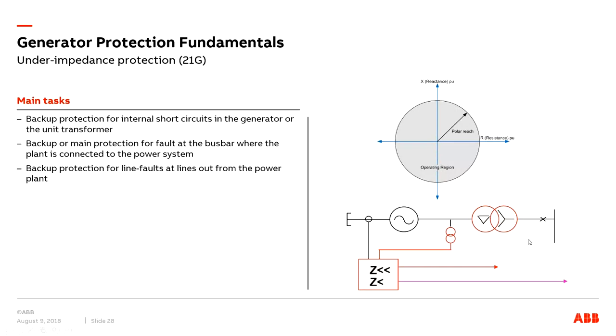Then we have the under impedance protection. The under impedance protection has two different tasks: detection and fault clearance of internal faults in case the main protection, that is the differential protection, fails. And the second task is to detect and clear an external fault, mainly in the case where the main bus bar or the line protection fails. In some power plants, there is no bus bar protection on the high voltage side of the unit transformer. In such cases, the under impedance protection is the main short circuit protection for bus faults. So you can see here, the under impedance functions are taking the CT and the VT input here, and then act as a backup.